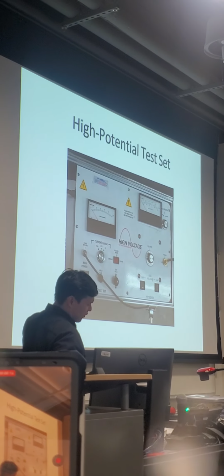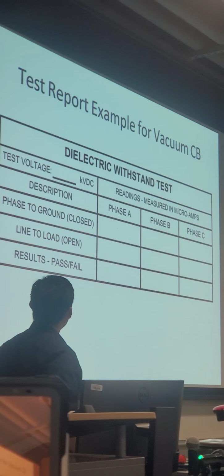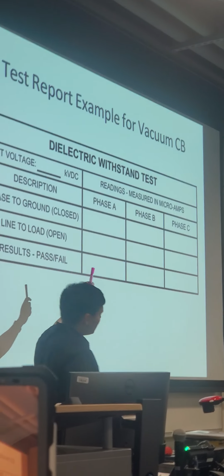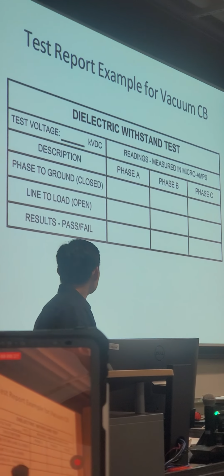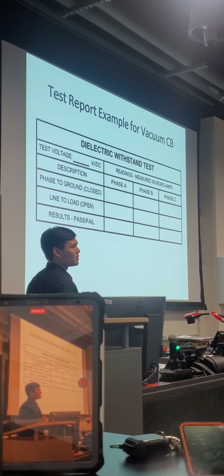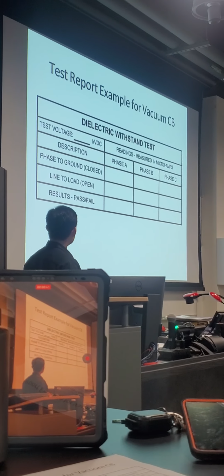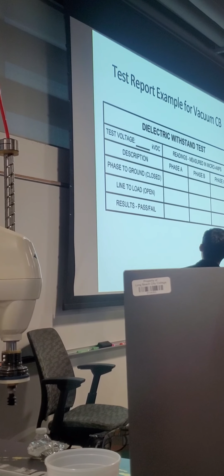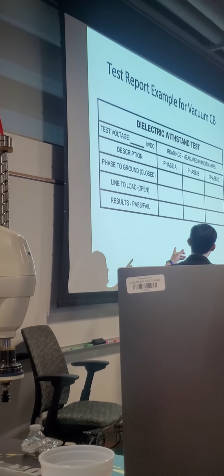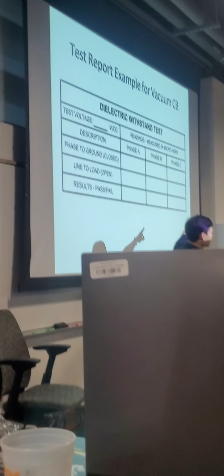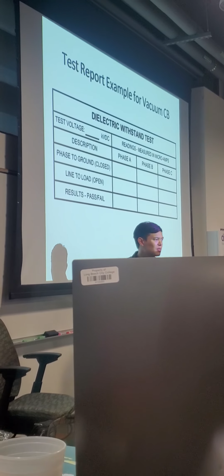When we perform the test, the values we're interested in are the milliamp or microamp readings, whether they're passing or failing. It's fine, because this is a go, no-go test. If it withstands, remember the dielectric withstand test, we know it withstands the voltage subjected to it, so it will pass. Now in broad numbers, if you see 5, 10, and 300, is that alarming?